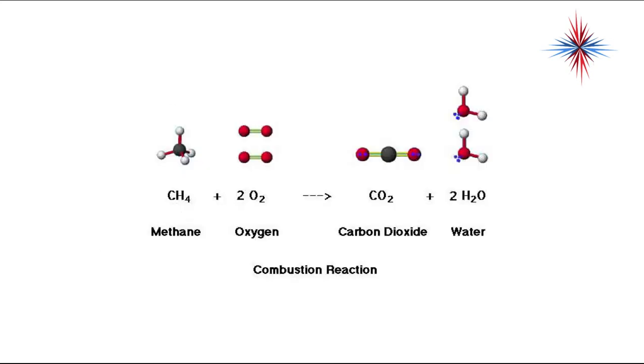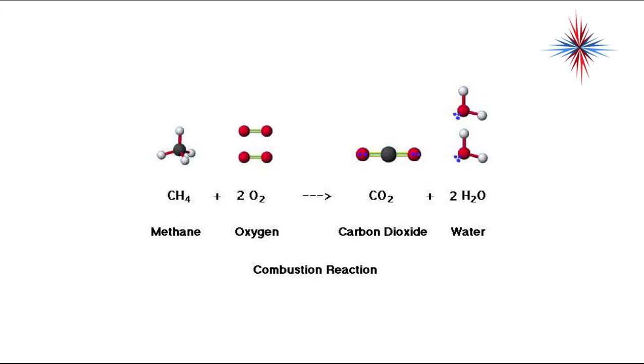It's a chemical reaction between methane and oxygen, caused by heat, that produces carbon dioxide and water. So the products of combustion are carbon dioxide, water, heat, and light. Stoichiometric combustion is the term for perfect combustion — the burning of fuel with the exact amount of oxygen needed to change the carbon and hydrogen molecules into water and carbon dioxide.